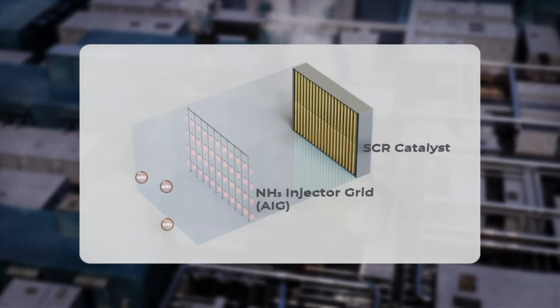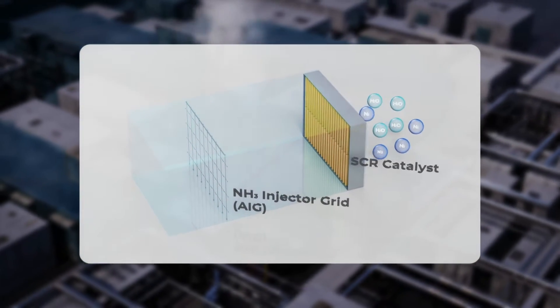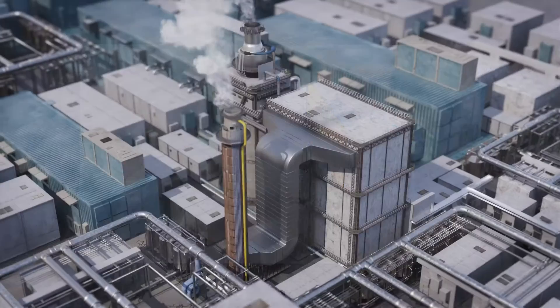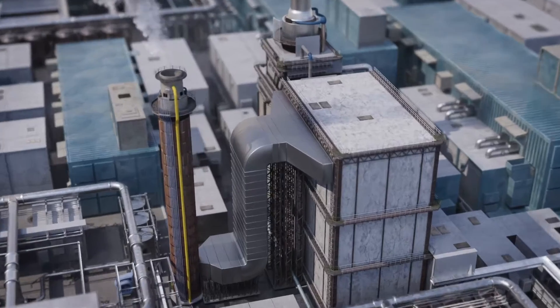SCRs function by injecting ammonia into the flue gas, which then passes through a catalyst module. This catalyst has fine pores that the flue gas and ammonia mixture must pass through before exiting the system for the reaction to occur.